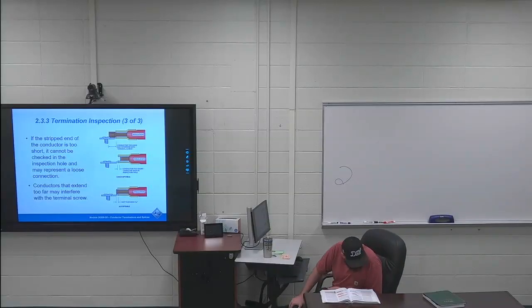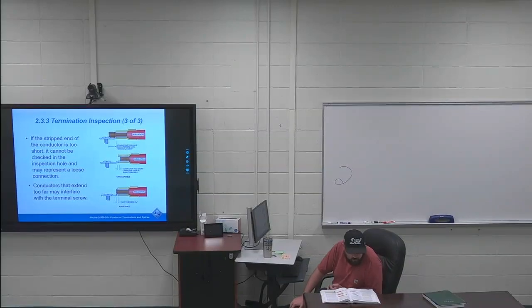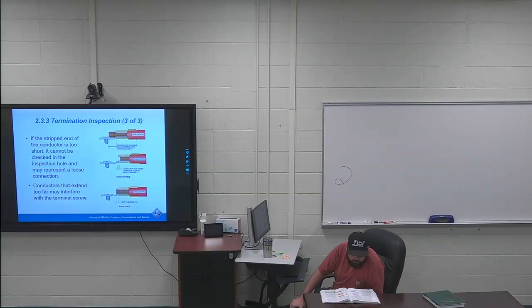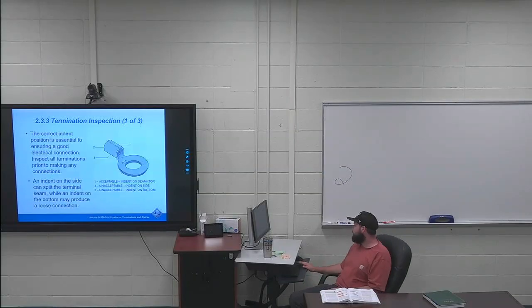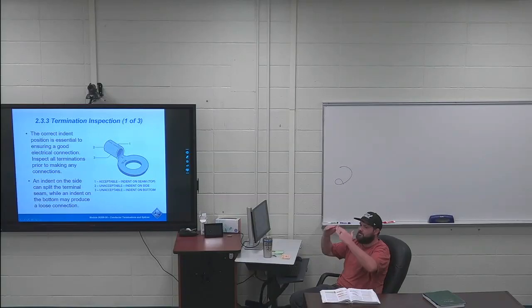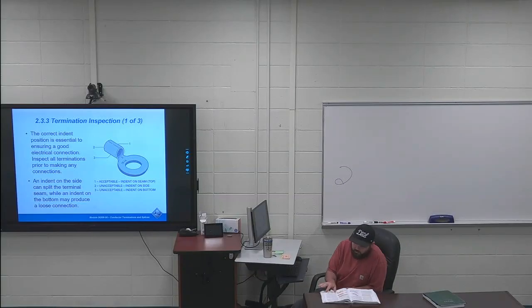Top right of page 22, 2.3.3 termination inspection. I always say do a tug test on these after you terminate them. Top right of page 22, second sentence is highlighted: the crimp barrel is designed to provide the best mechanical strength when the indent is properly placed on the top seam of the barrel. All of these have a split seam on them. This is where you want to put your indent, not on the back. I used to think the back was where you put this indent. Nope. You want your indent on the top. You want this to fold over and clamp down onto your wires, creating a good termination.